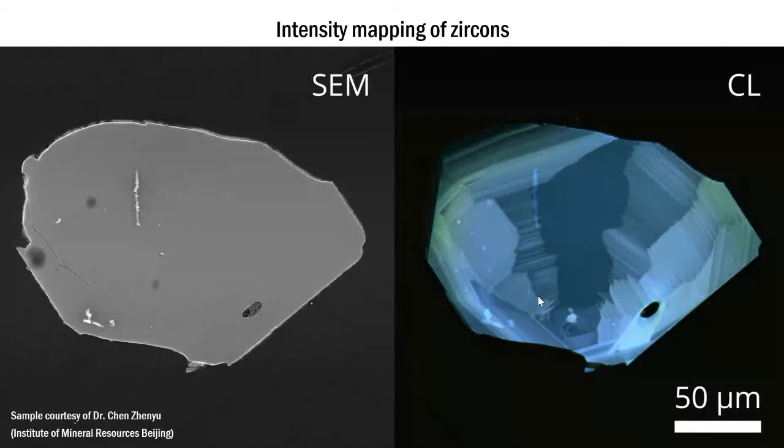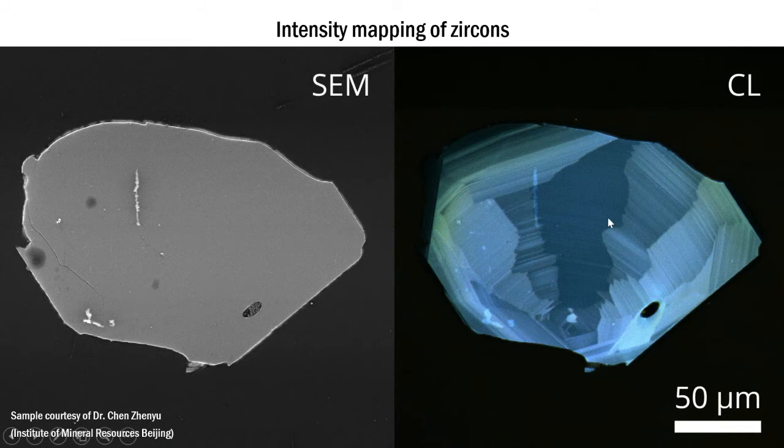This is one such example from geology. It's a zircon or zirconium silicate, a mineral which is very popular because it's used for geological dating. This CL intensity map of a zircon crystal that you see on the right side shows the zonation or bands that you can see are not visible in the SEM image on the left. So the contrast is very different in CL. This is valuable information for geologists and it helps them select the crystals of importance for further analysis like mass spectroscopy. Now this image was acquired at 10 kV and 500 picoamps. You can see that at 10 kV, there is sufficient CL signal. Now there would be some broadening or loss of resolution because it's a high energy, but given the size of the features and the size of the zones, this broadening is not significant. So at higher energy, say 20 or 30 kV, this blurring becomes more significant.